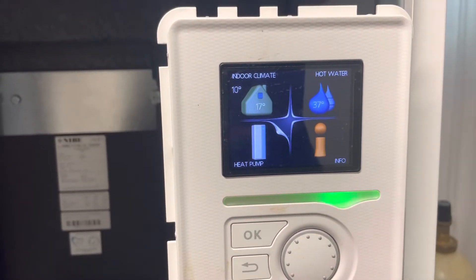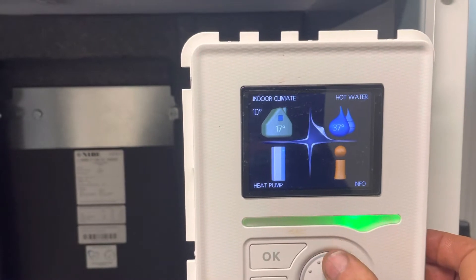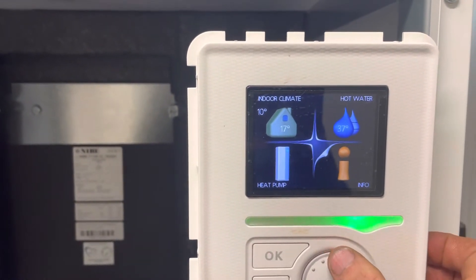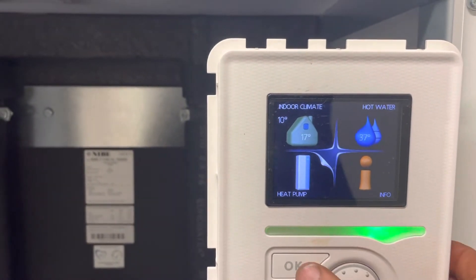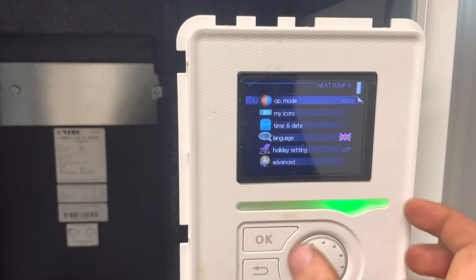To put an NIBE F1145 or F1245 into Add Heat mode to use the immersion in case you have a fault, go to heat pump on the bottom left by using the rotational dial, press OK, and go into Op mode.